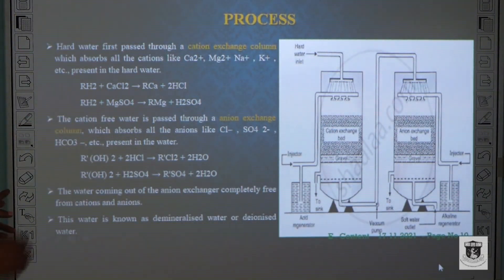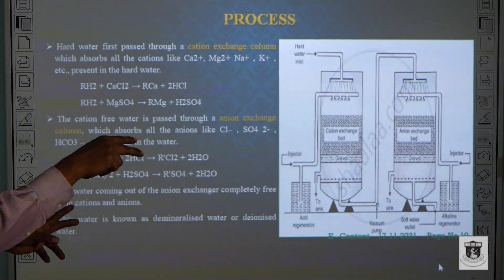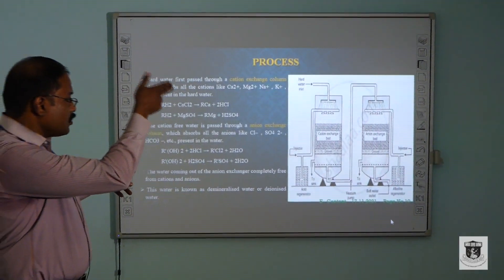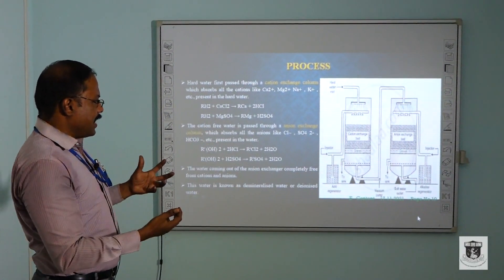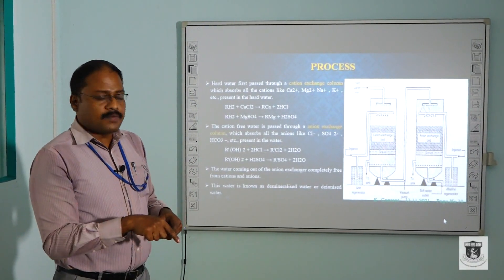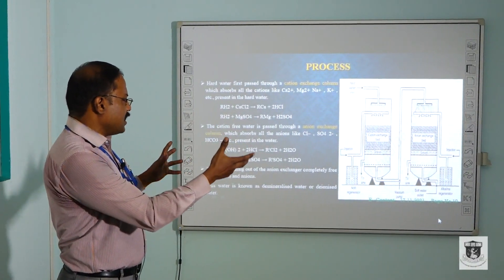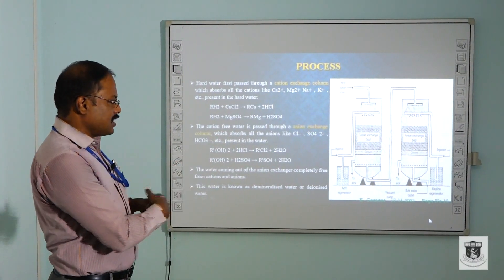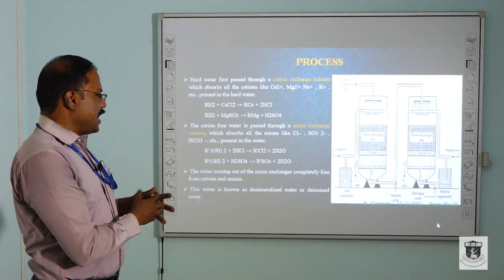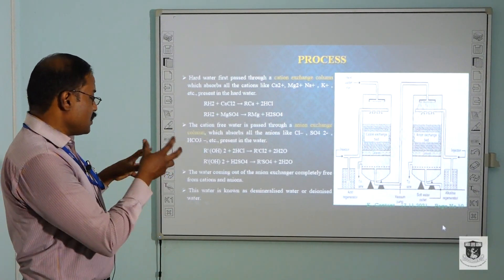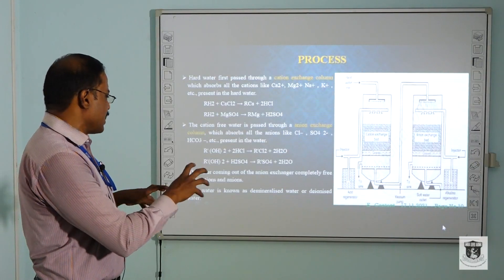After passing through the cation exchange bed, the cation-free water is passed through an anion exchange column, which absorbs all the anions like chlorides, sulphates, and whatever else is present from the hard water, converting them to RCl₂ on the resin and releasing water molecules in the purest form. Ultimately, the water coming out of the anion exchanger is completely free from cations and anions. This water is known as demineralized water or deionized water.